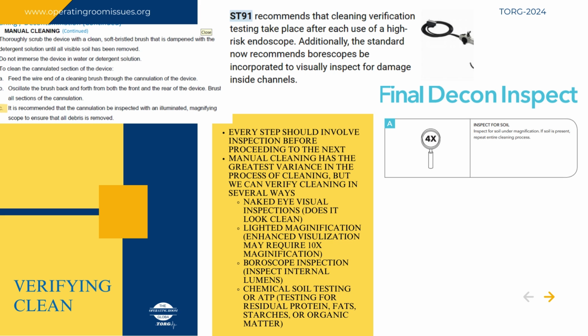So you'll see in the left-hand corner right there, it says decontamination and cleaning of the manual process. If you look at section C that I have highlighted, it tells you it is recommended that a cannulation be inspected with an illuminated magnifying scope to ensure that all debris is removed. Without that borescope, how do we do that? There is no other way to look inside of those cannulas.